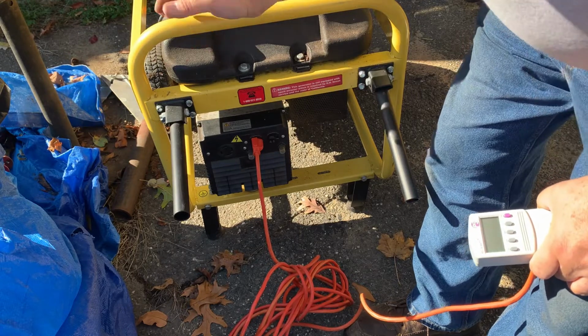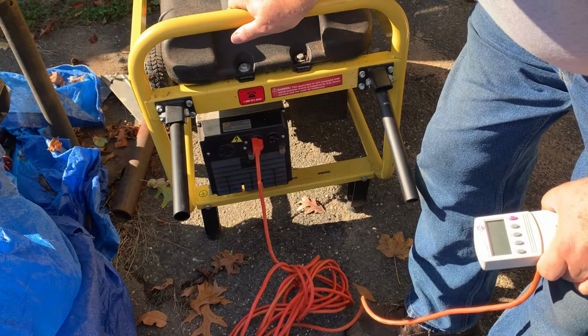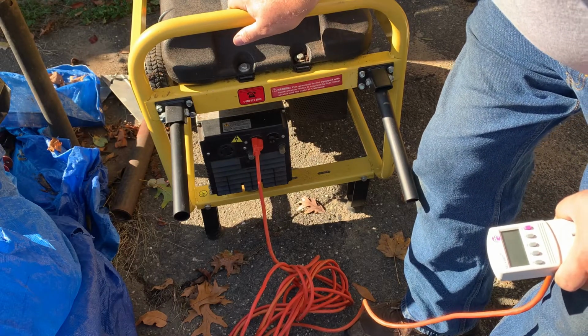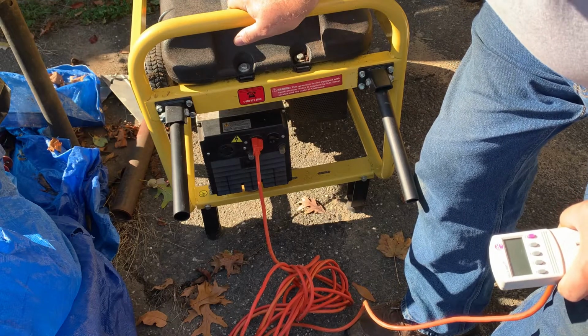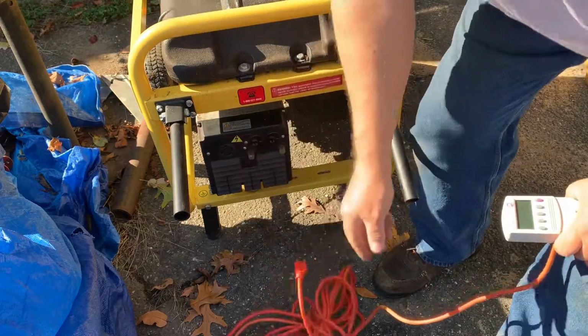But thanks again to Mr. Condon. James, you're the best. And something simple like this, when you have a capacitor and you're getting low voltage, when it's a capacitor type and not the brush type, just change a capacitor. And I tell you, win-win for me and win-win for the customer. All right. I like that.